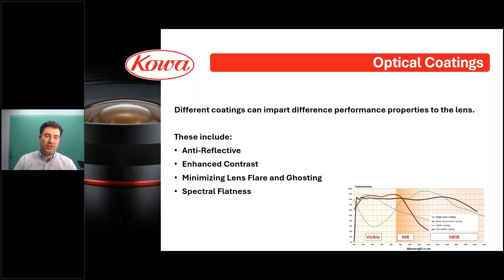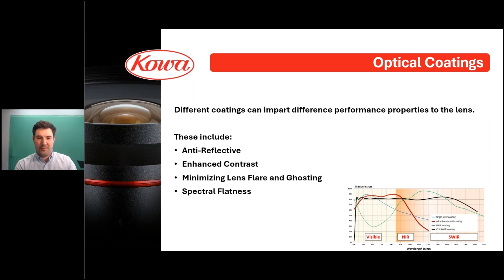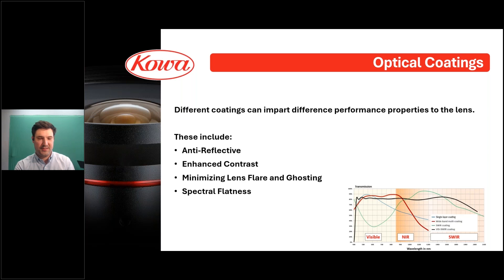Coatings can also minimize lens flare and ghosting. Since we're capturing images and converting them into spectra, flare and ghosting will show up as artifacts in your spectral data. Additionally, some coatings are designed to ensure flat wideband transmission — for example, this vis-SWIR coating, which is really good for hyperspectral imaging, ensures transmission will be very flat across the whole band. This makes calibrating your data easier and gives you a nice consistent signal. Ensuring your lens coatings are suitable for the intended spectral range will help you achieve more reliable imaging results.